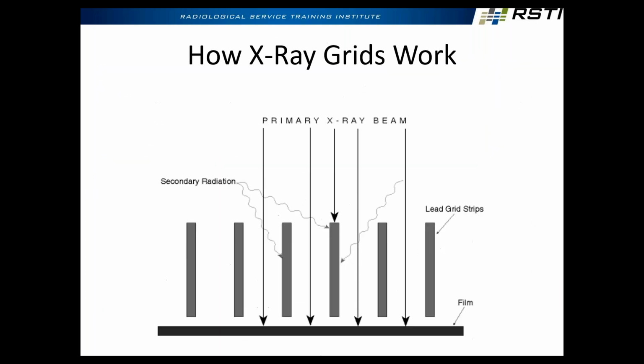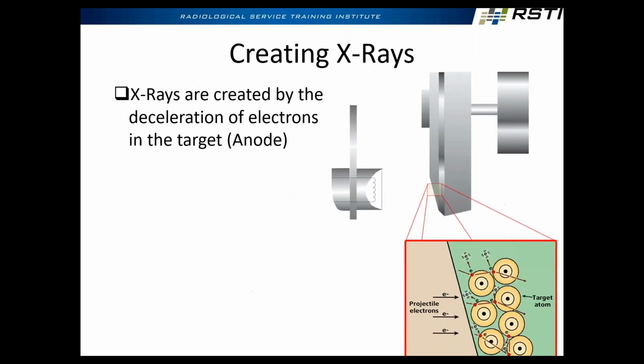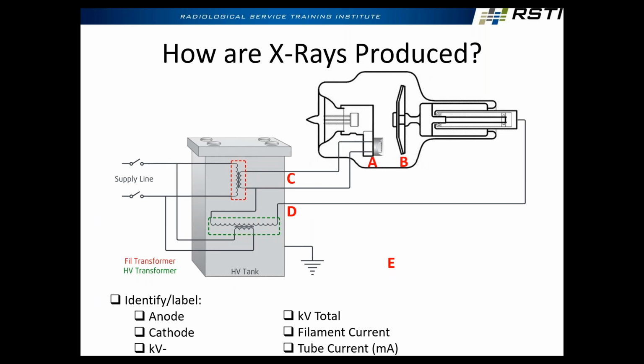So going back to my X-ray tube from earlier. This is mA, going between there, agreed? If I change the mA, I'm going to change the quantity. I have more or fewer photons. I didn't change the power of those photons, which means the balance of penetration and absorption didn't change, but I have more or fewer of them. So it didn't change the contrast because the penetrating ability and the absorption balance remained exactly the same, but it got lighter or darker. Does that make sense? Same thing with time. If you look on that chart, time also only affects density because, again, the number of photons is going to make it lighter or darker. They're not any stronger. They're not any weaker. They're not penetrating more or absorbing more. It's just a pure number, lighter or darker.